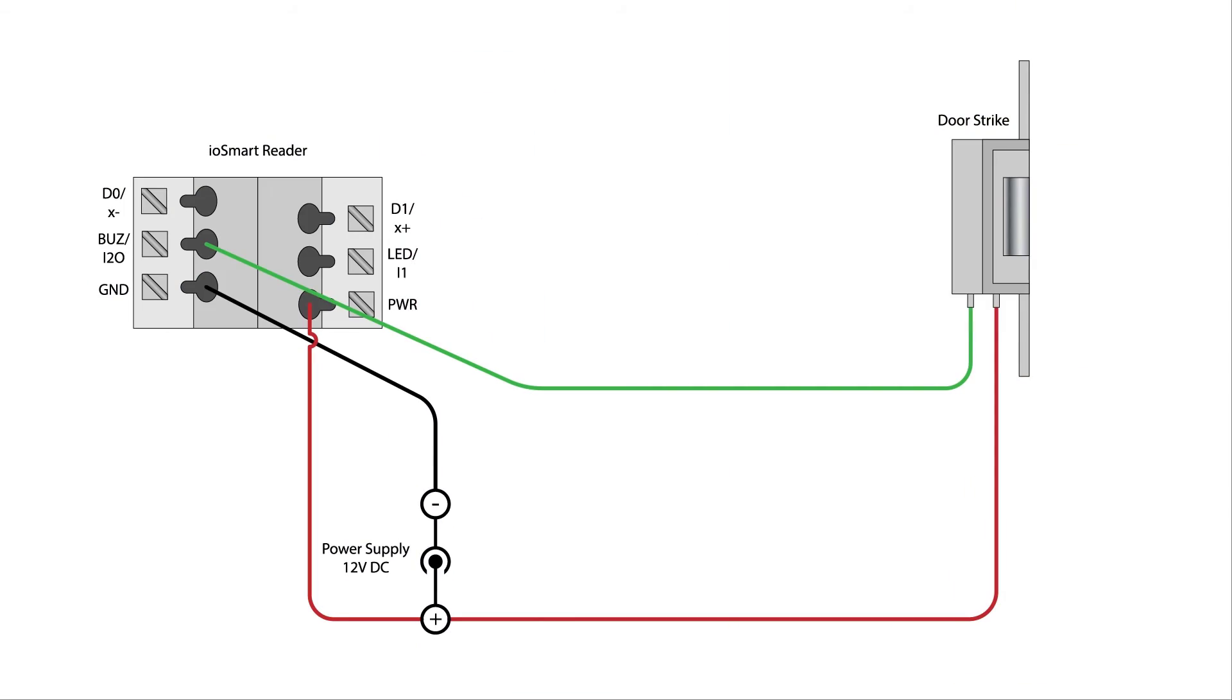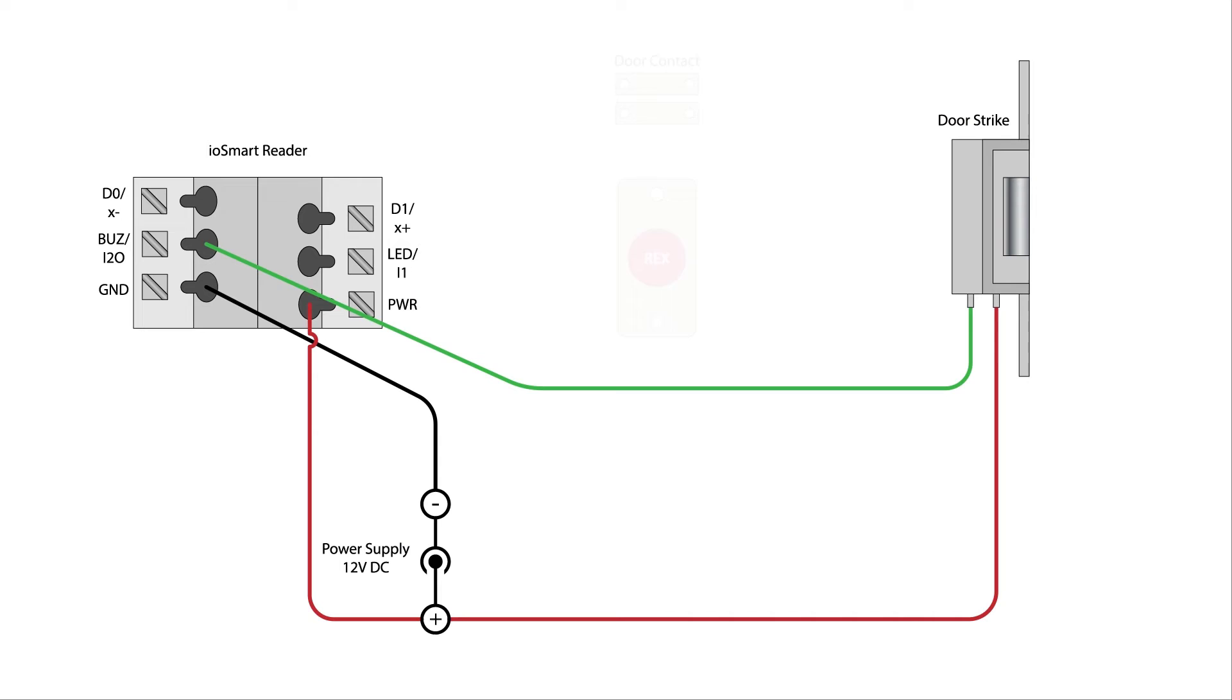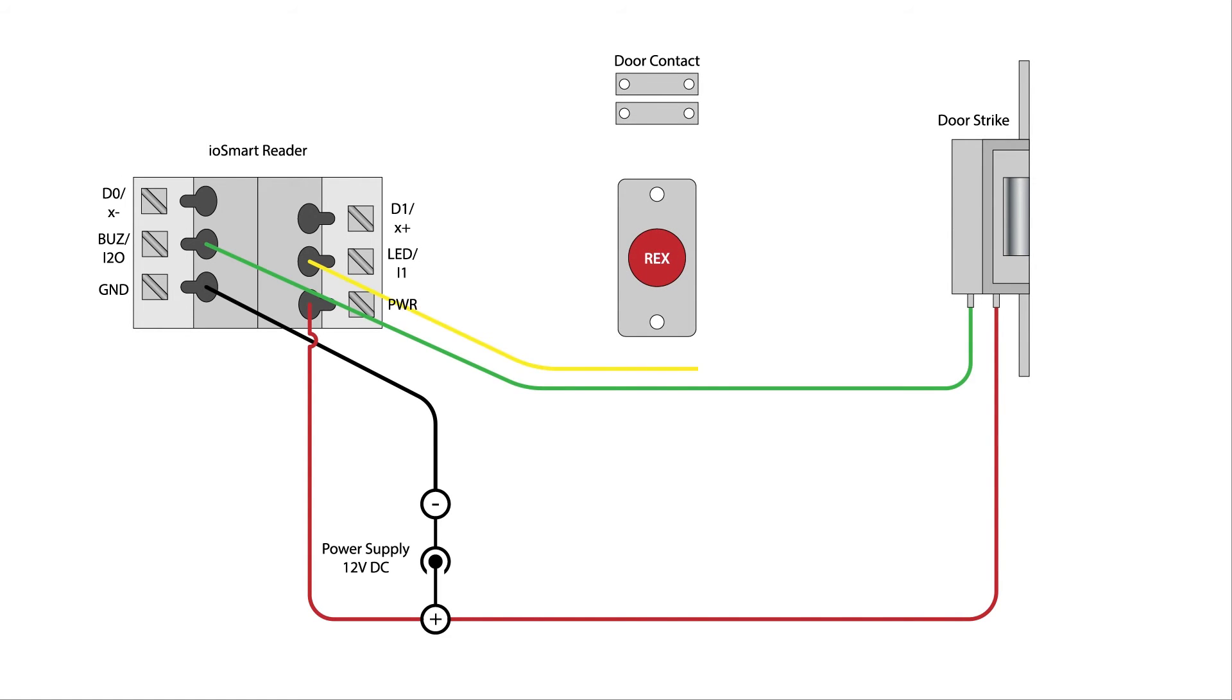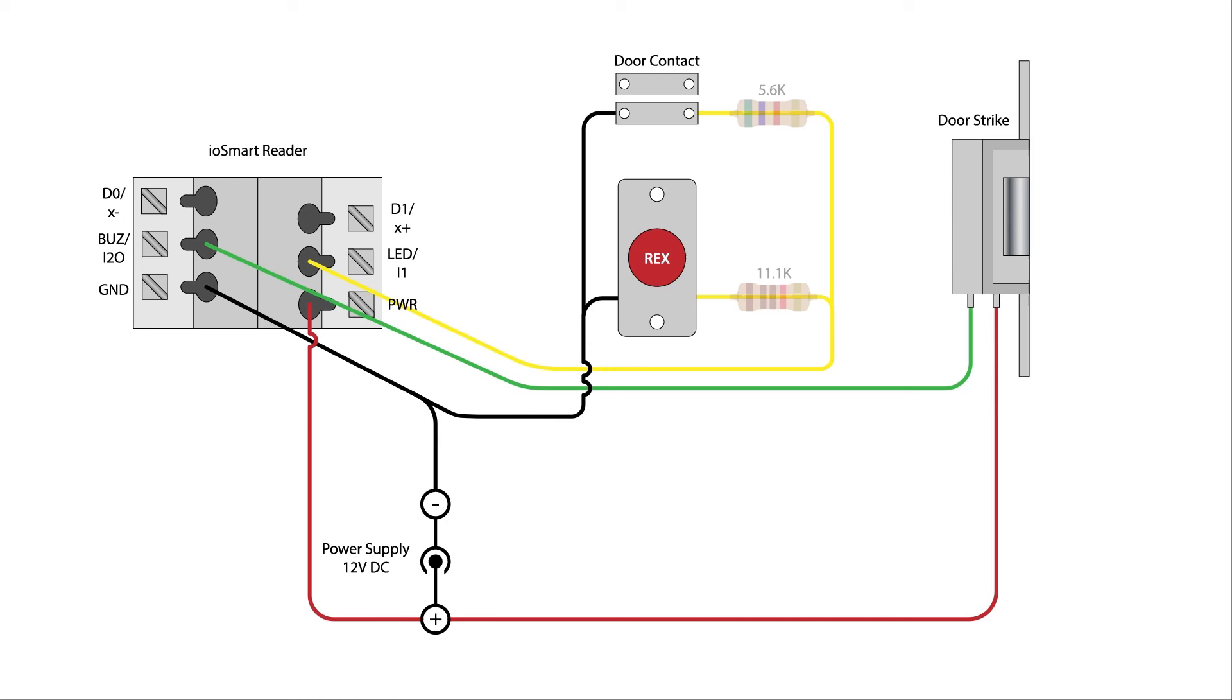If you opt to use a request to exit device, a door contact sensor, or both, you may also connect these in parallel to the I1 terminal on the reader. The use of a REX and contact sensor are optional but must be wired for normally closed operation if used. Use 5.6k ohm and 11.1k ohm resistors in series with each as indicated.